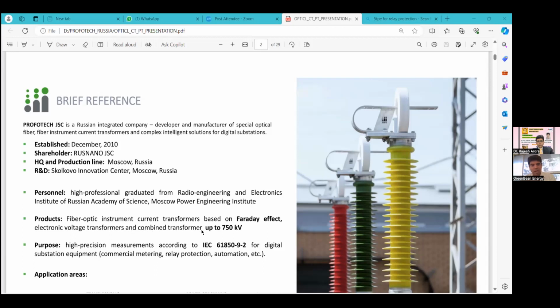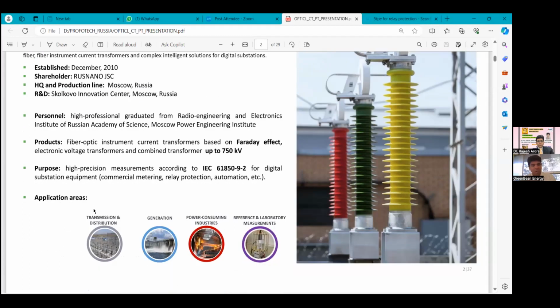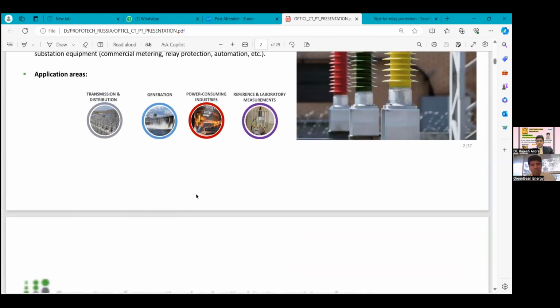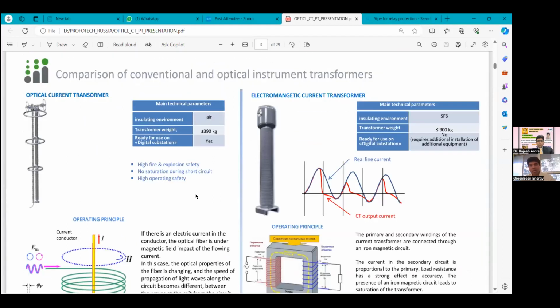The purpose is high precision measurement according to IEC 61850-9-2 for digital substation equipment. The purpose is commercial metering, relay protection, automation, etc. The application areas are transmission and distribution networks, generation, power consuming industries, reference and laboratory measurement. Here is a comparison.